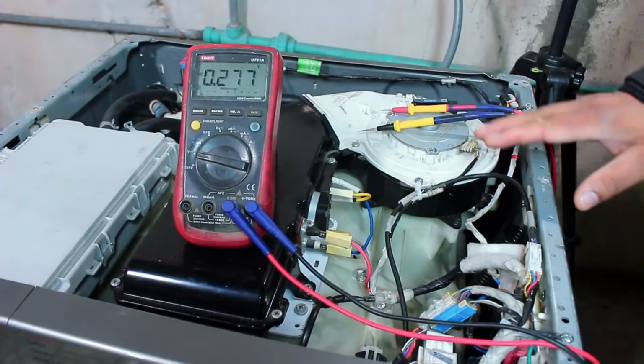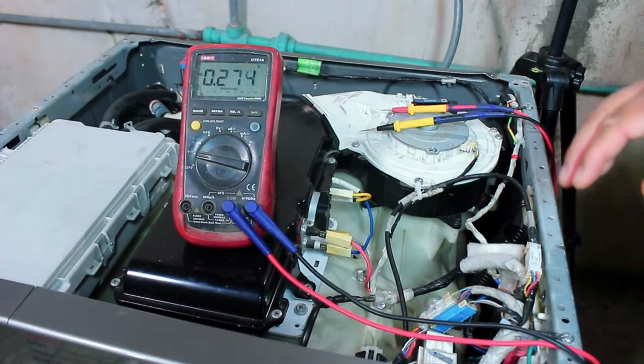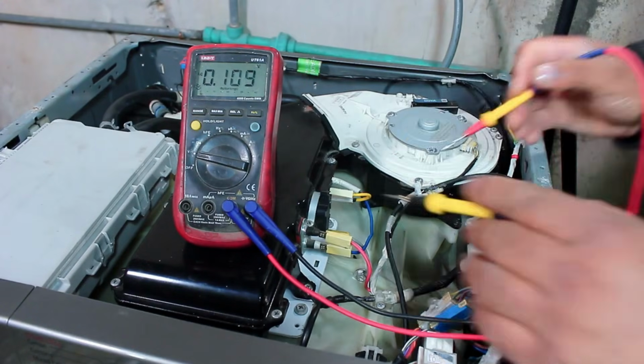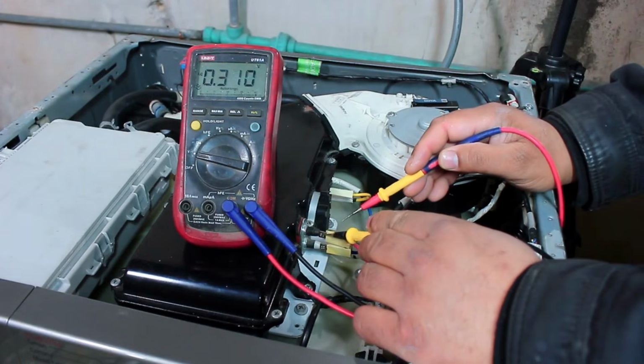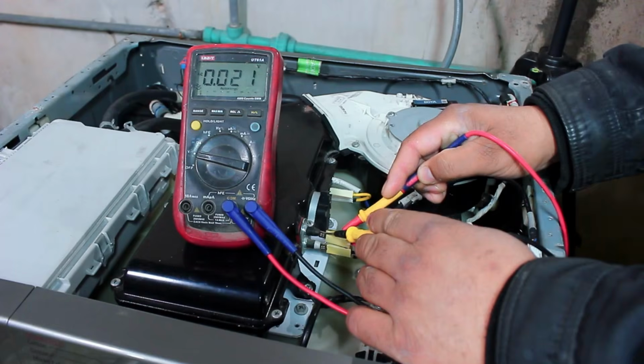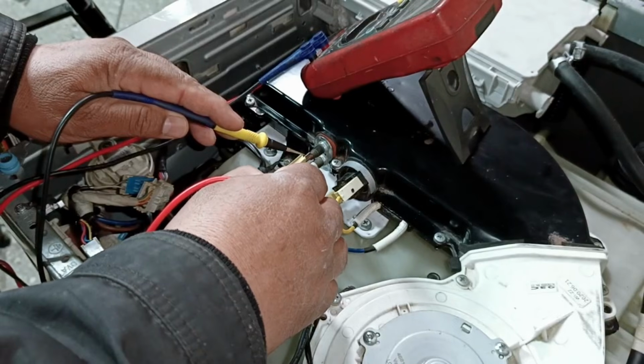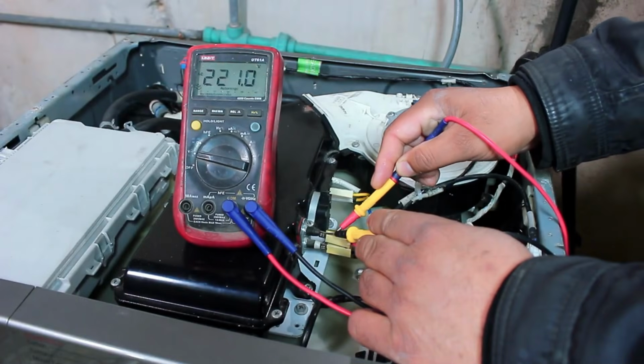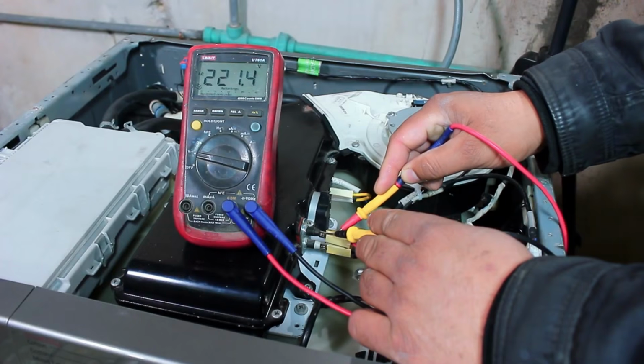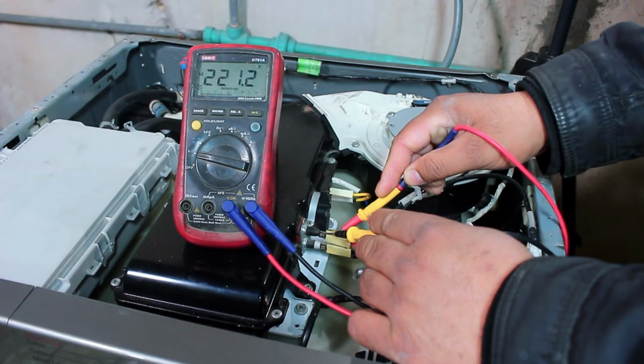Just now, it drained the water once. The motor stopped, and now the function has stopped again. Let me check once more. It's possible that the heating element has turned on again. But as you can see, there is still no voltage present here. Now you can see the voltage has arrived. Around 221 volts AC is now present here. That means the heating element will start working.